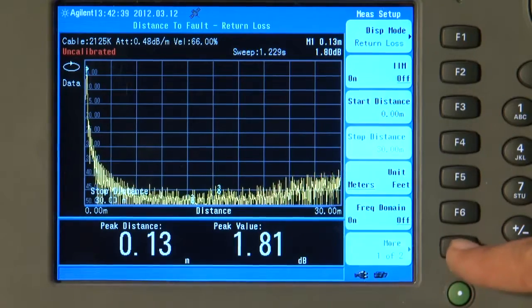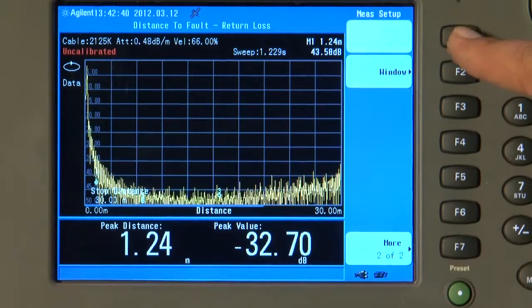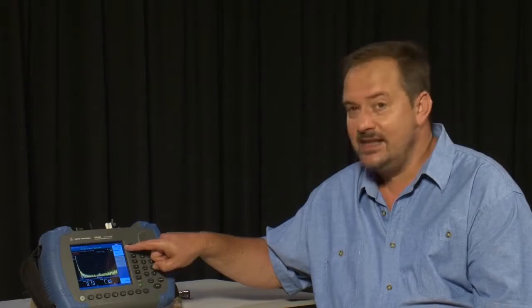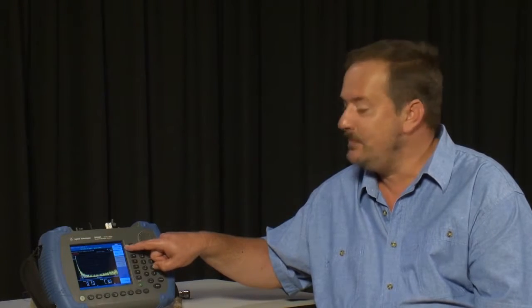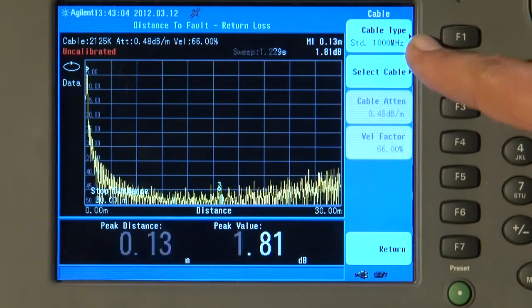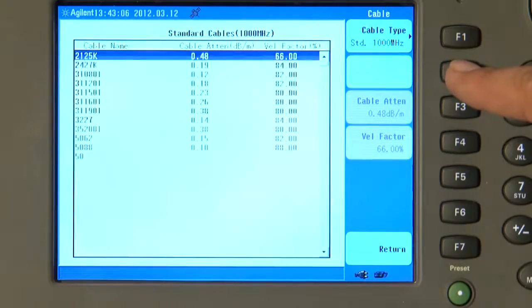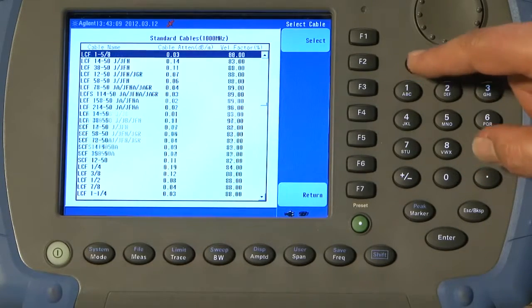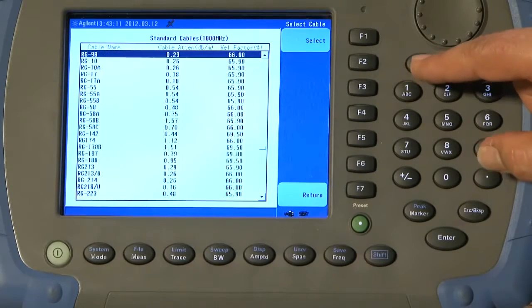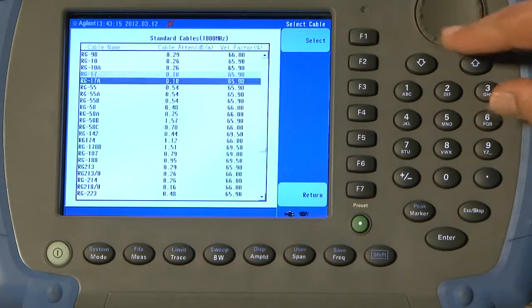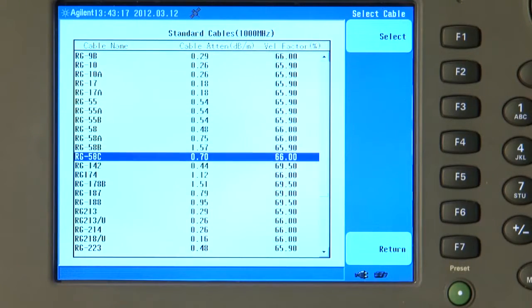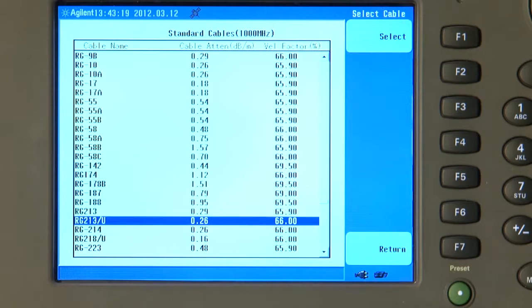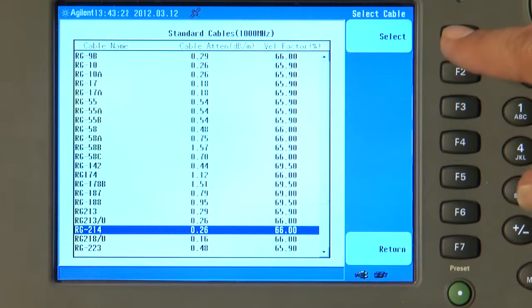So we press the More button, press Cable Specification. We can select the frequency at which the cable specifications were measured, in this case 1 GHz. And if I press Select Cable, we can scroll down through a very long list of all the most common commercially available RF cables. In this case, I am going to select RG214 and press Select.